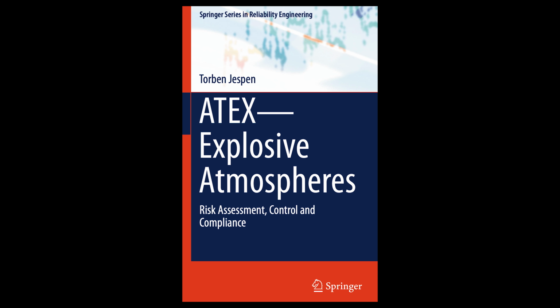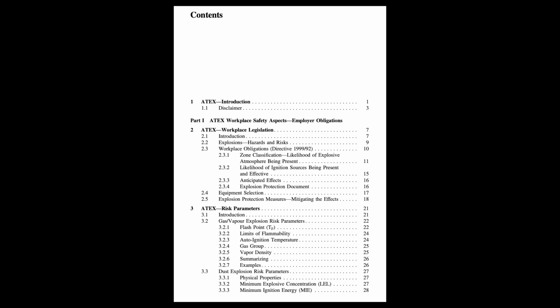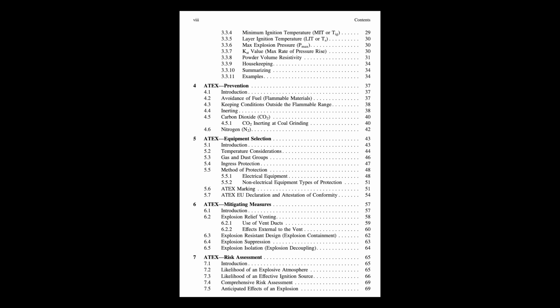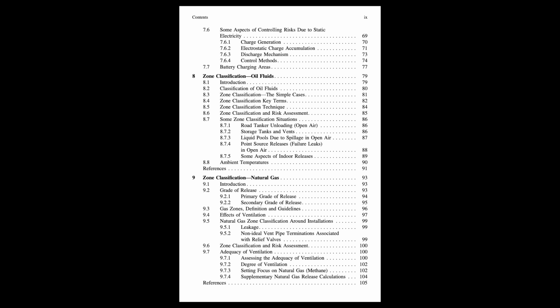And how does the process work? How do you do an IHA? Typically, you'd use a systematic approach, often based on a standard list of potential ignition source types. The guide mentions 12 basic types from standards like EN ISO 80079-36. You consider sources within the equipment, like bearings overheating, and also those potentially introduced by the process, like static from flowing powder. Okay, a structured check. Yes. For each potential source identified, you estimate the likelihood it could become an effective ignition source during normal operation, an expected malfunction, like a seal failing, or a rare malfunction, like two independent faults occurring.